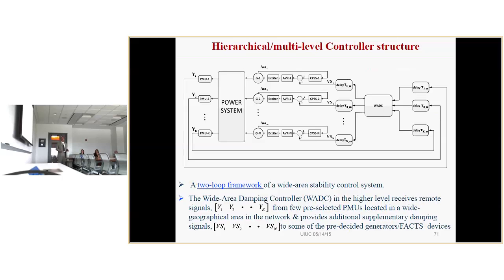So there are two architectures. One is decentralized, the other is centralized. What we worked on initially was the centralized architecture, where we have one wide area damping controller, getting data from the field, which may be power oscillations in the line, and giving commands to the individual excitation systems of the generators, as a supplementary controller. Over and above the conventional PSS, you are getting an additional signal for effectively damping out the inter-area oscillations.